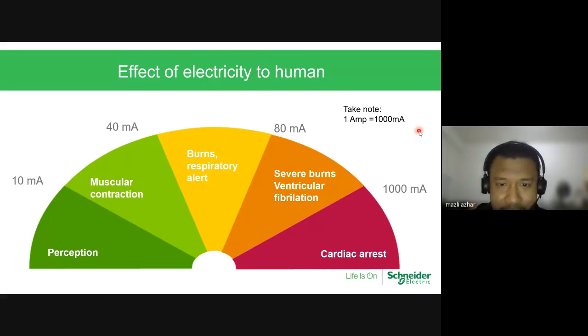But what people do not know is that when there is a leakage in the electrical network system, it can travel from the washing machine, from your fridge to your water heater while you are using it. Okay, so it has happened for the past few years. People get electrocuted. Why? Because they don't put additional protection. The ELCB at the water heater is not functioning. So if they put another 10 milliamp protection, then we have additional protection for the whole system. And then just to remind you, water is a great electricity conductor. So it may happen. When things happen, it will happen.